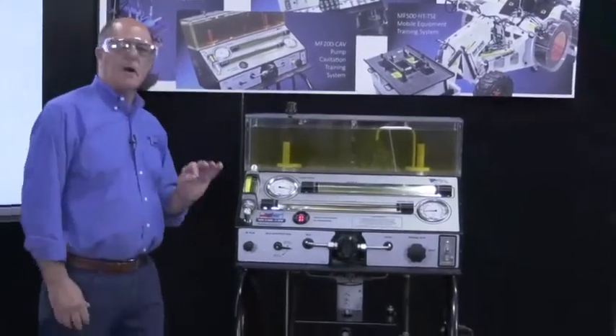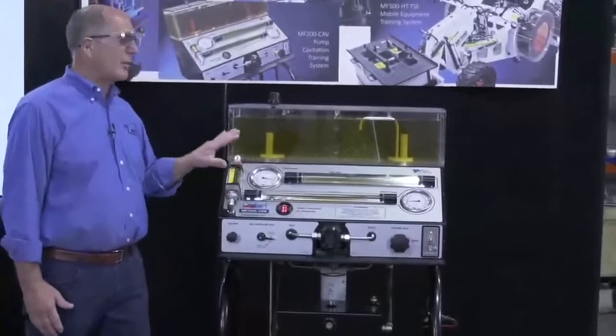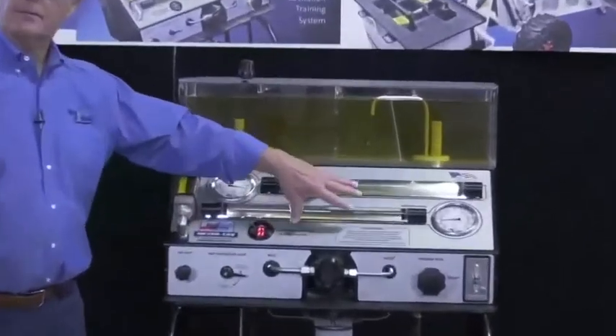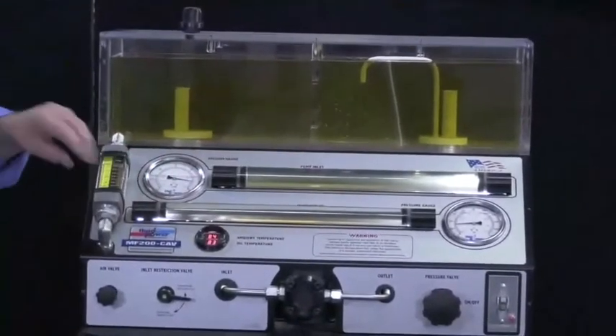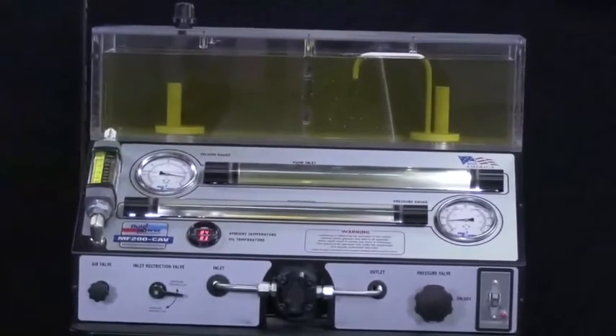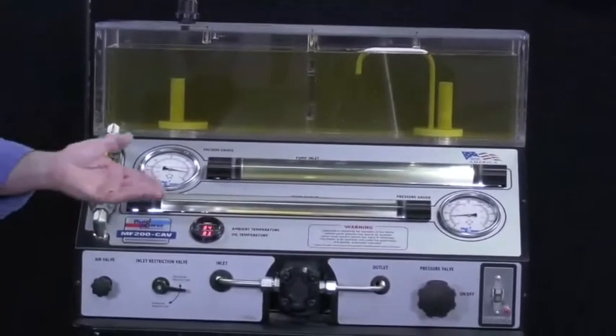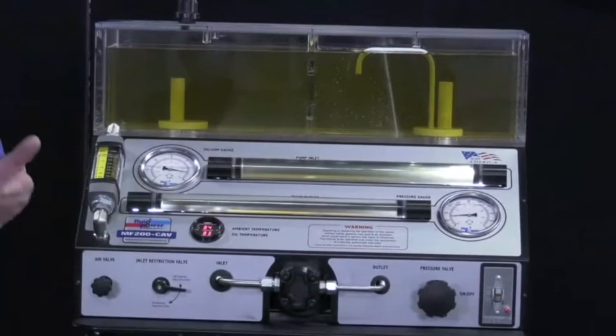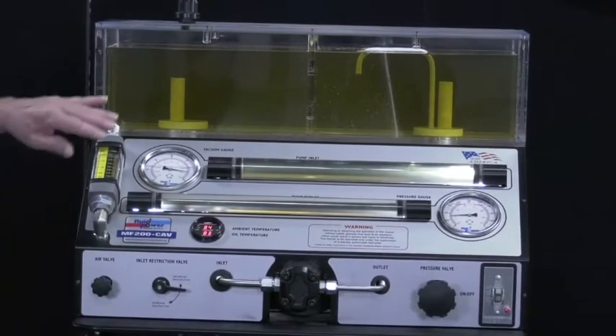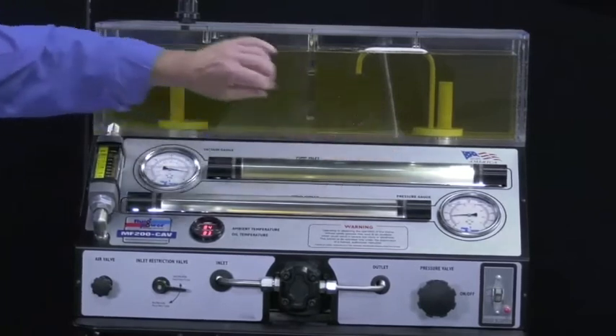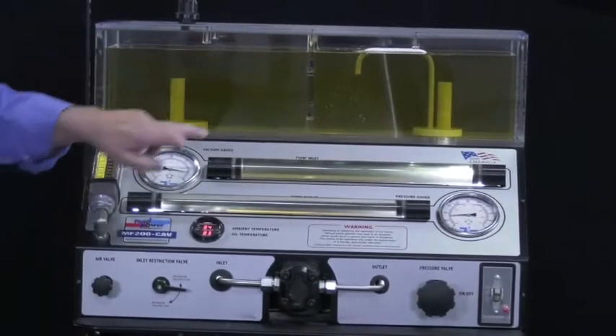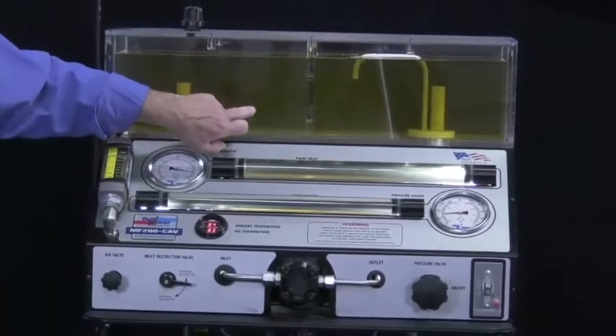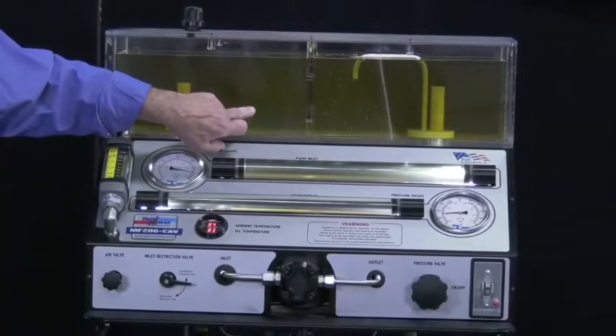Interestingly, I can see here I've got 1.8 gallons a minute flowing through these lines. In other words, what's interesting is you cannot actually physically see this flow. You don't want to see flow. Flow, if you can see it, it's turbulence. You don't want that. You want laminar flow. The other thing you'll notice is that every 60 seconds, I'm exchanging in this hydraulic reservoir 1.8 gallons of oil.